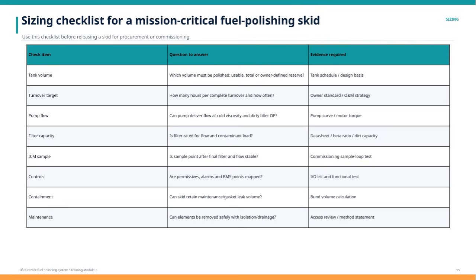First, consider the tank volume. You need to know exactly which volume must be polished. Is it the usable volume, the total, or some owner-defined reserve? This should be verified against the tank schedule or design basis documents. Next, define the turnover target. How many hours are required for a complete turnover, and how often should this process occur? This is typically determined by the owner's standards or their operations and maintenance strategy.